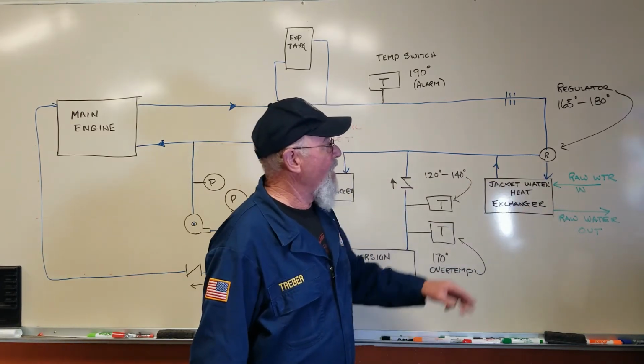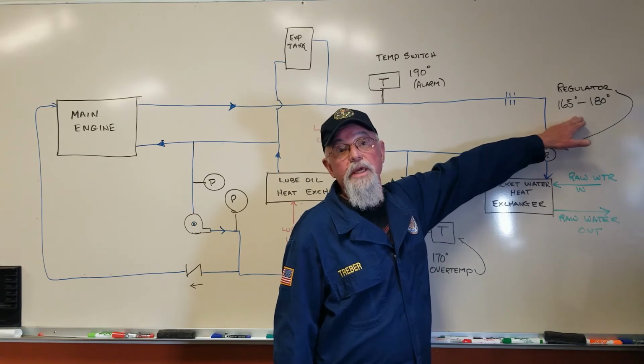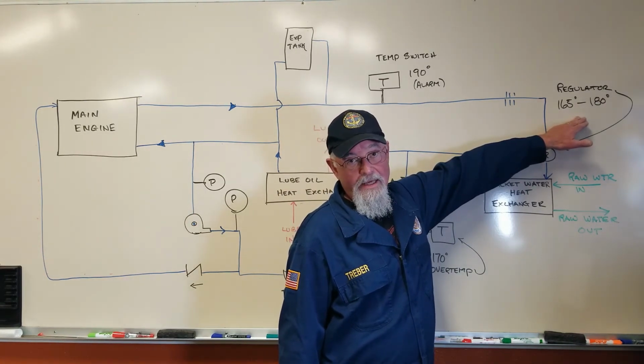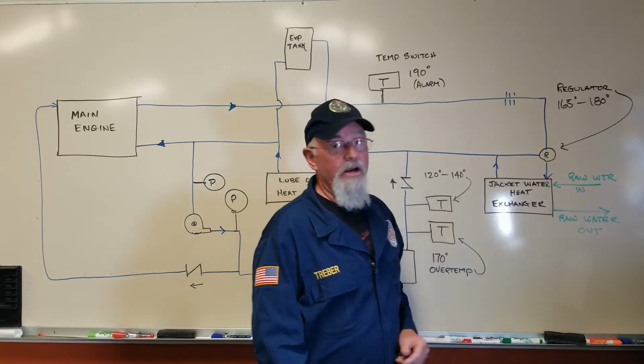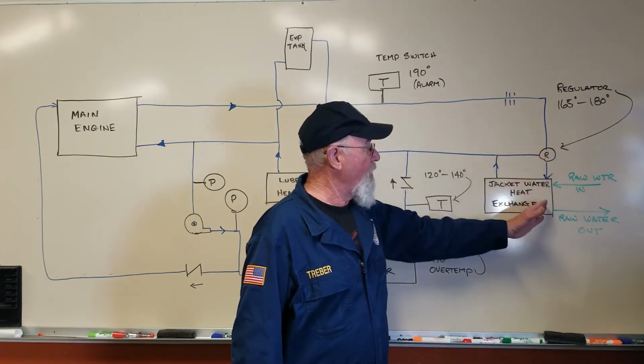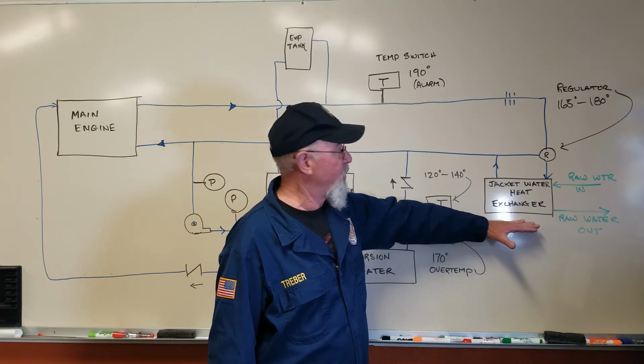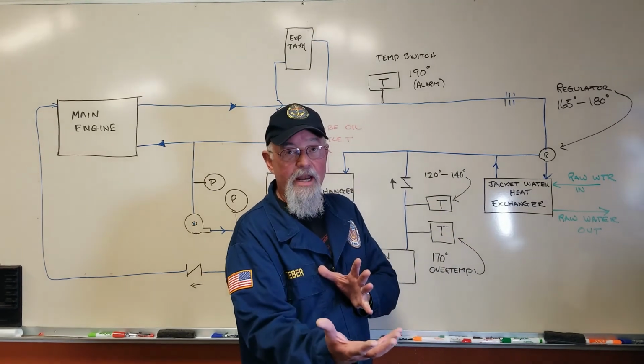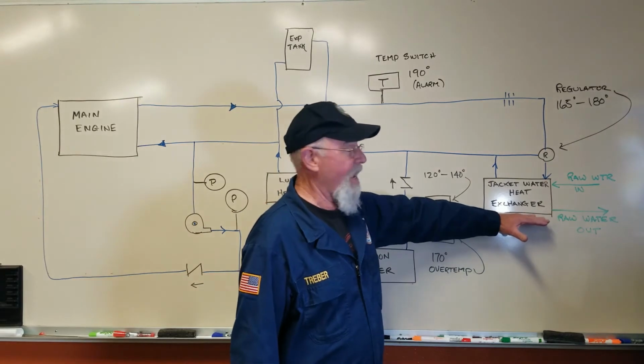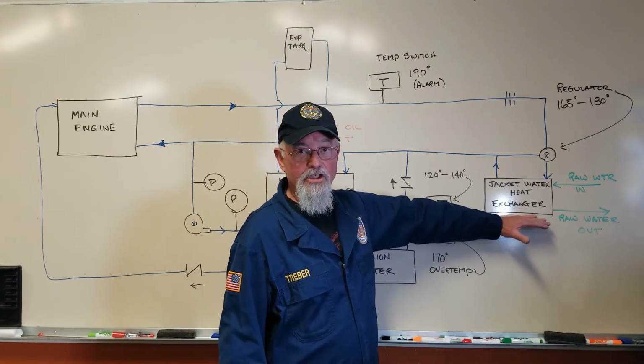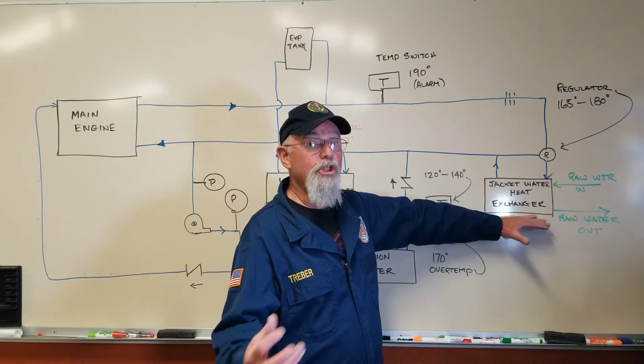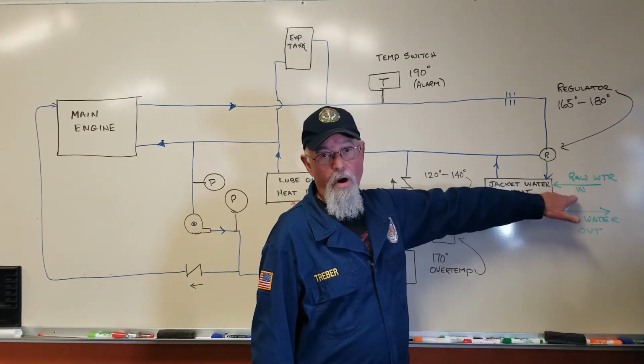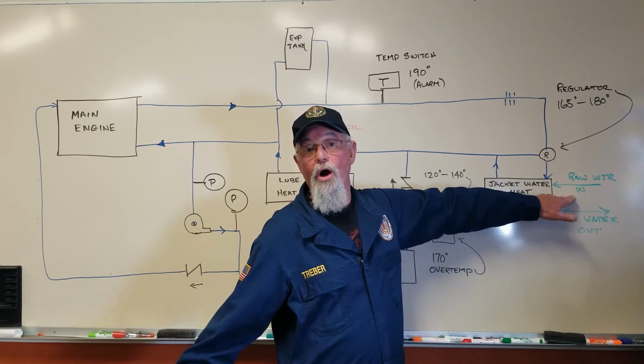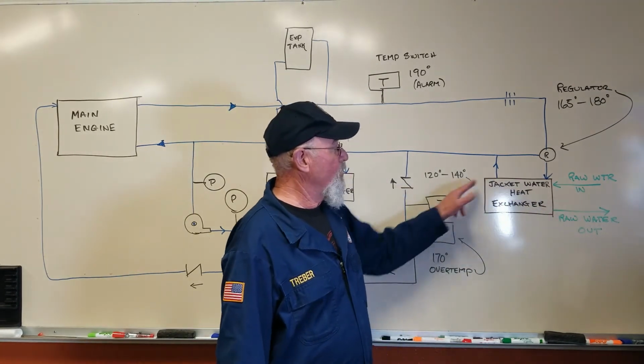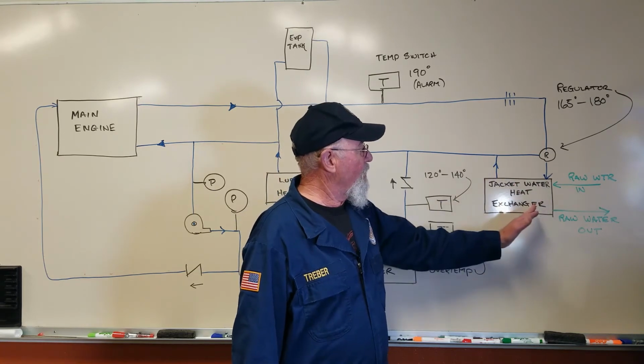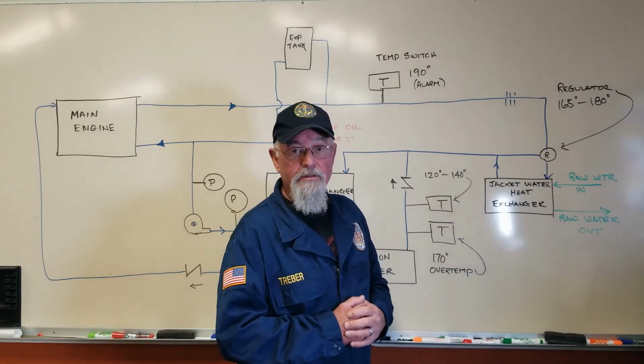But once the engine's in operation, our normal jacket water temp is going to be a little bit higher than 180, right? So at 180 degrees, this regulator is 100% open, sending all the jacket water through the jacket water heat exchanger, so we can get rid of some of that heat. So the same thing, it's a tube and shell heat exchanger. So going through the tubes is the raw water: seawater, river water, whatever raw water source you happen to have. Through the outside of the tubes is the jacket water.